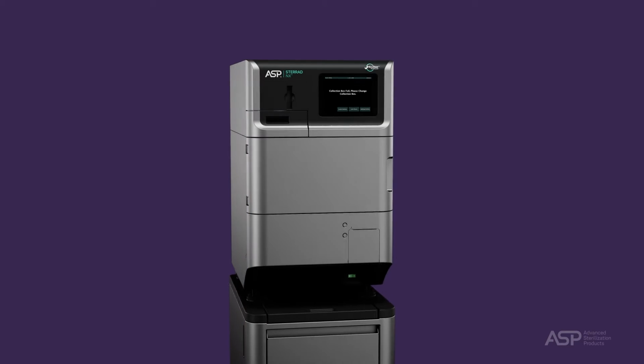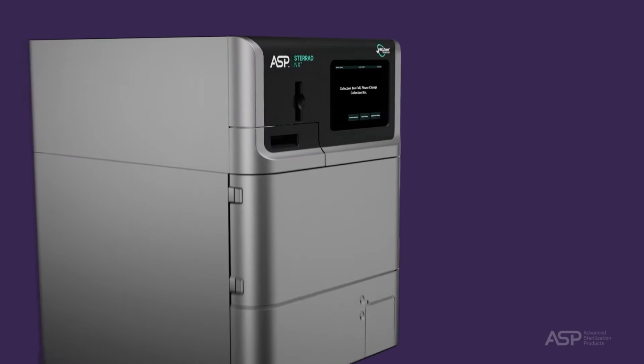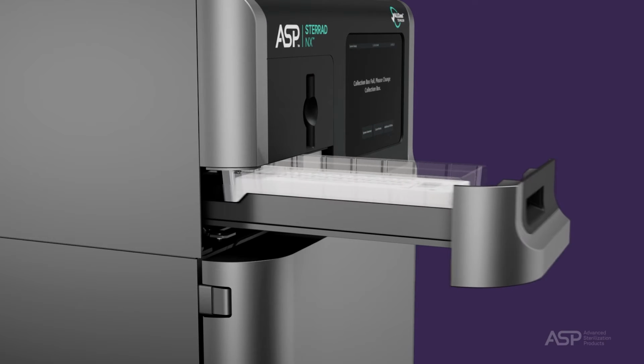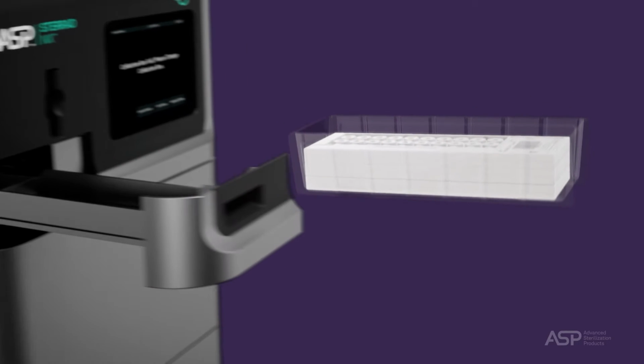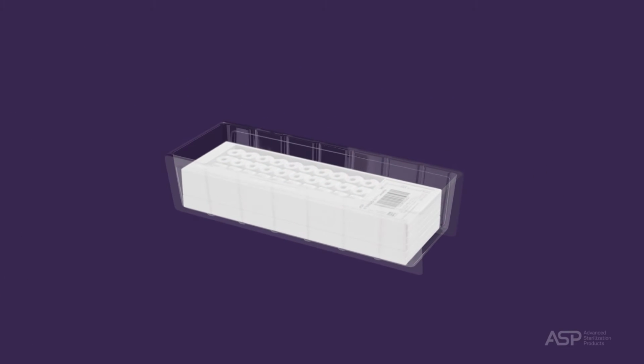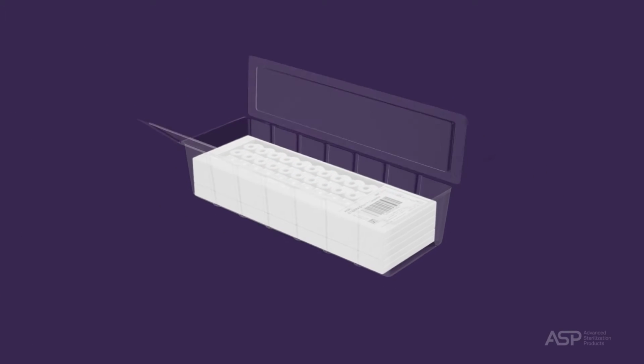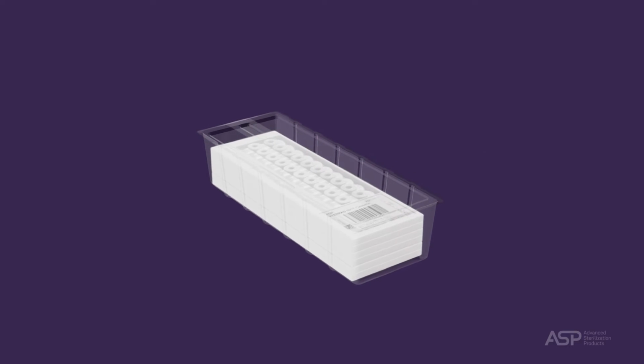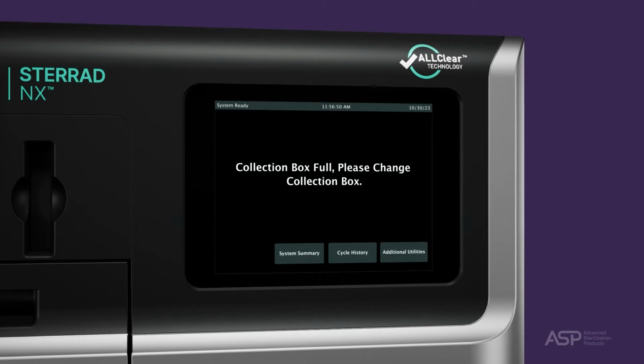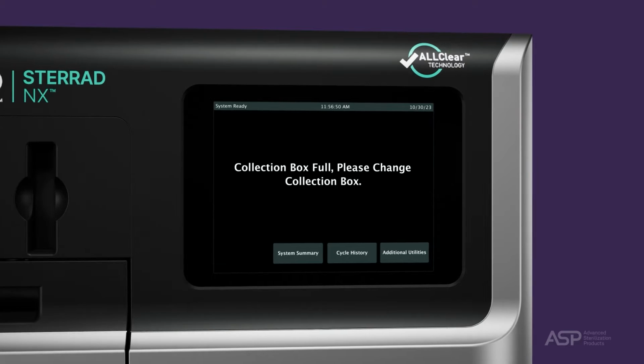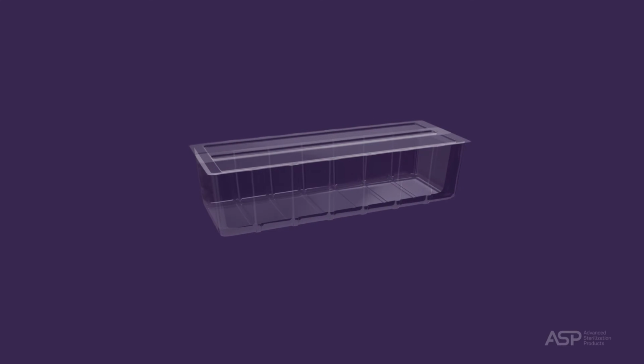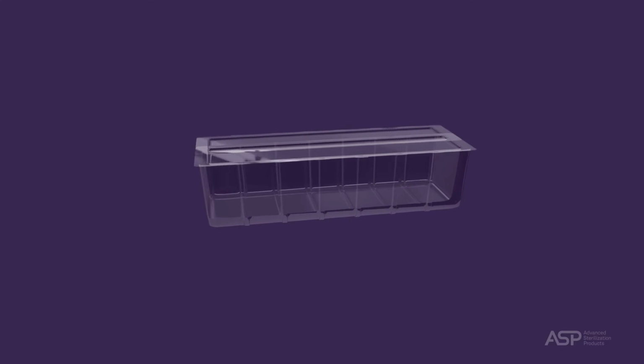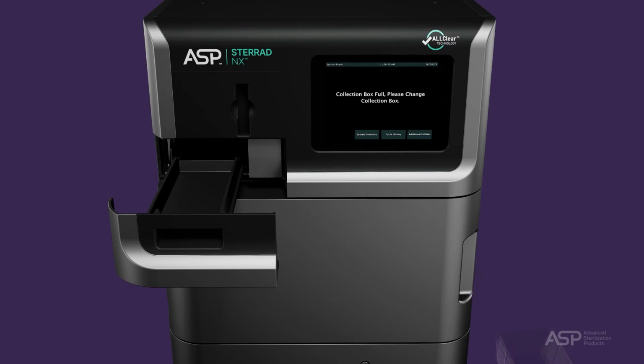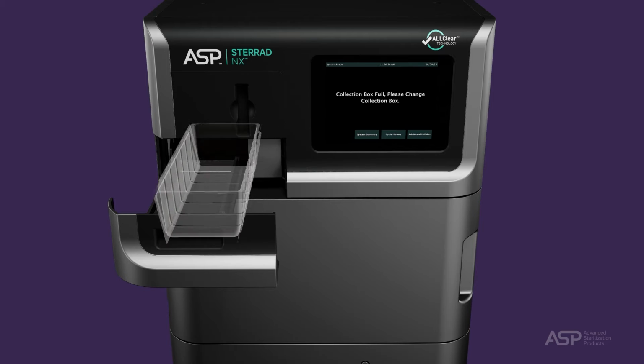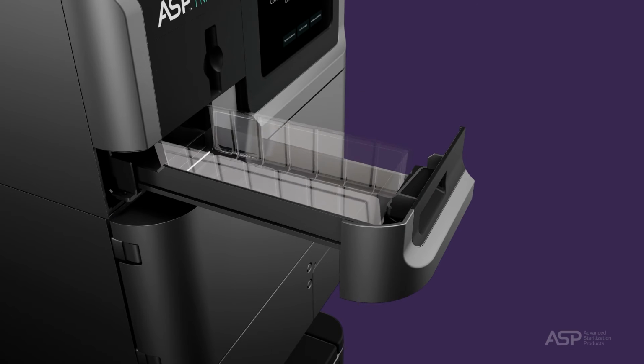When a cassette is empty, the sterilizer automatically moves it to the cassette disposal box in the collection drawer. When the cassette disposal box contains 3 cassettes, it is full, and you must dispose of the full cassette disposal box. The screen displays a message instructing you which actions to take next. For safety reasons, you must use the cassette disposal box to dispose of cassettes. Never reuse a cassette disposal box. A new cassette disposal box must be assembled and inserted into the drawer.